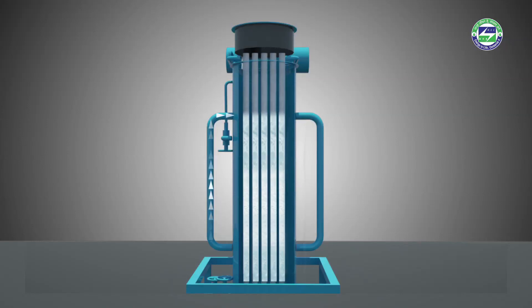During thawing, the solenoid controls hot gas from the condensing system to enter the freezer. Within one minute, the long tube of ice comes out and is cut by a rotating cutter, then discharged through the opening in the water tank.